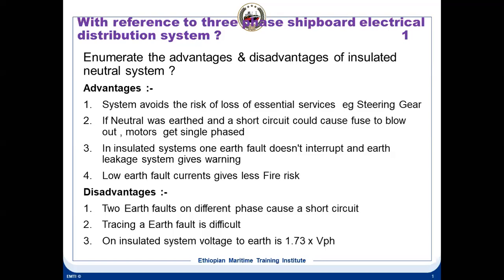Second thing, in an insulated system, one earth fault does not interrupt, and earth leakage gives warning. Suppose one phase gets earthed, like R, Y, B phase, one phase is grounded. There will be a leakage current to the ship's hull, but the machinery will continue to run. Okay. And low earth fault current gives less fire risk.